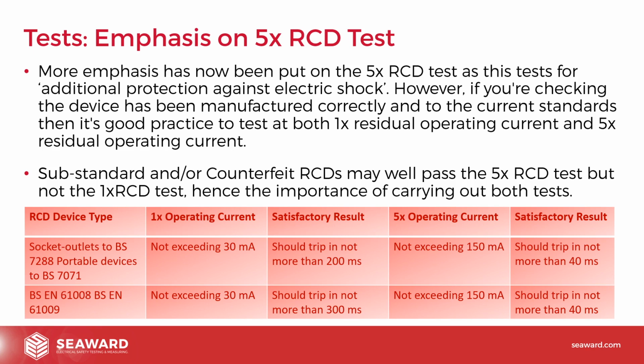However, if you're checking that the device has actually been manufactured correctly and is to the current standards, then it's good practice to do a 1 times test as well. So we generally recommend, and on our products we have, a 1 times test and a 5 times test, and obviously they'd be repeated at 0 and 180 degrees as well.